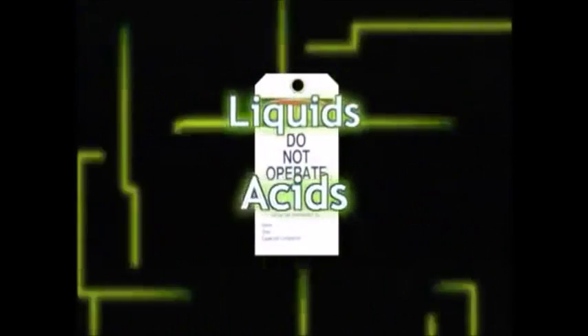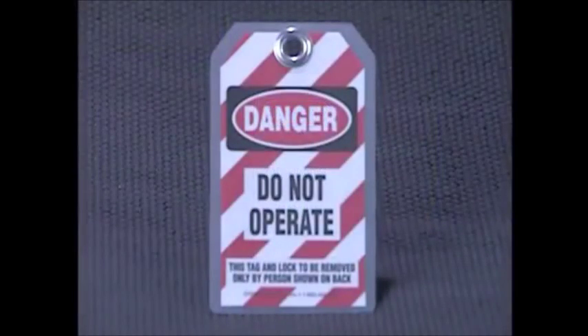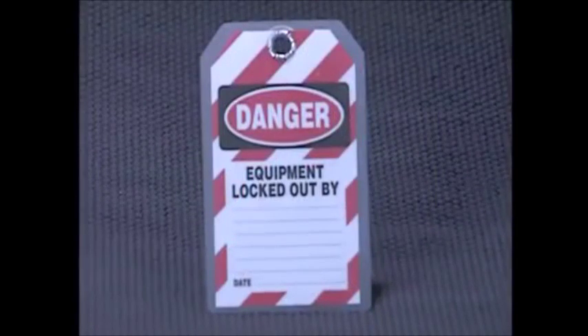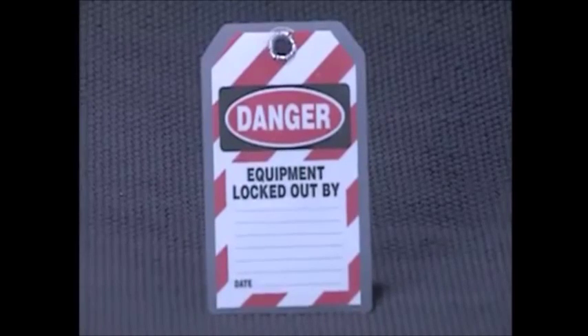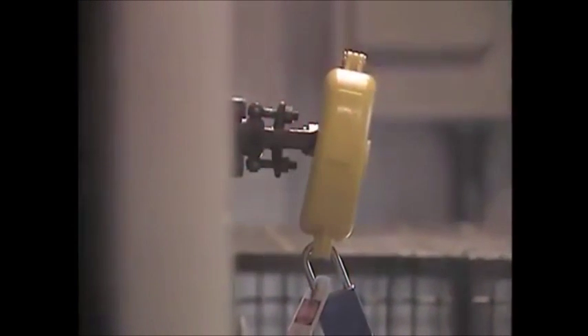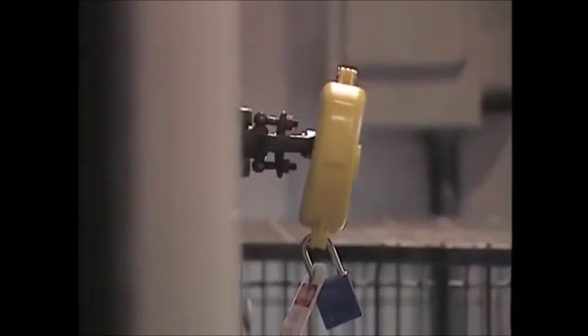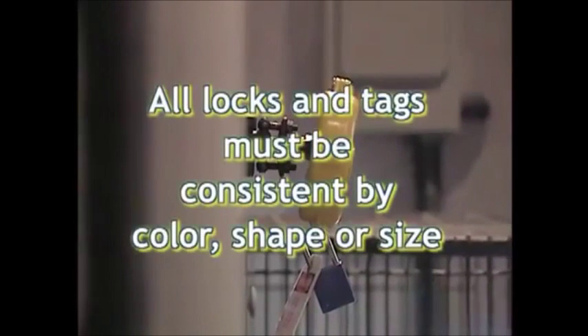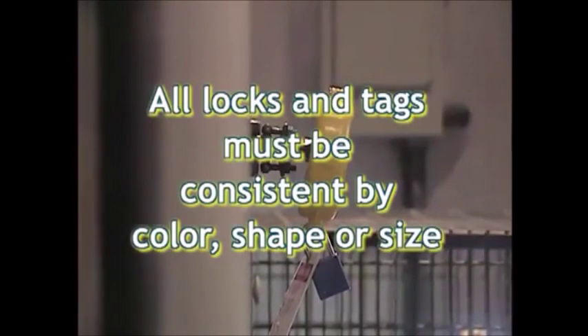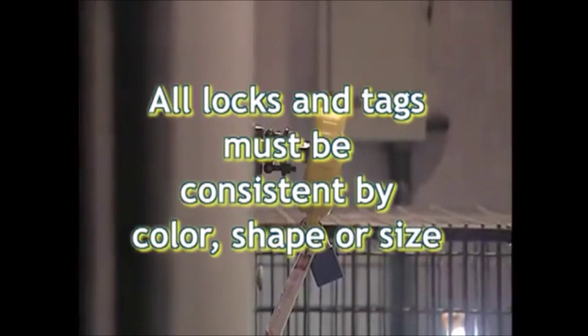The OSHA standard allows a tag in the place of a lock only if the tag-out provides the equal protection of a lockout. Tags must be made so that if they are exposed to liquids or acids, they can still be read. Tags must have a warning on them that has the same wording and look in order to make them easier to recognize. Tags must be attached securely so that they can't accidentally fall off. All locks and tags must be consistent by color, shape, or size.